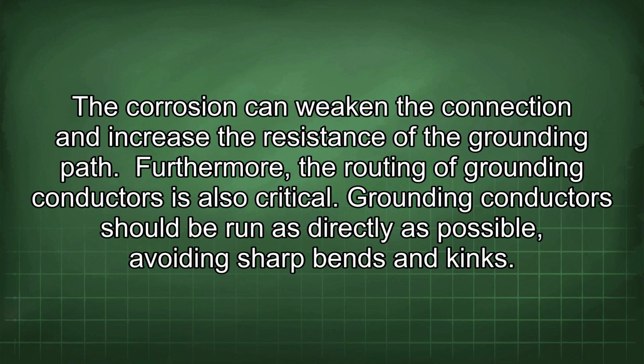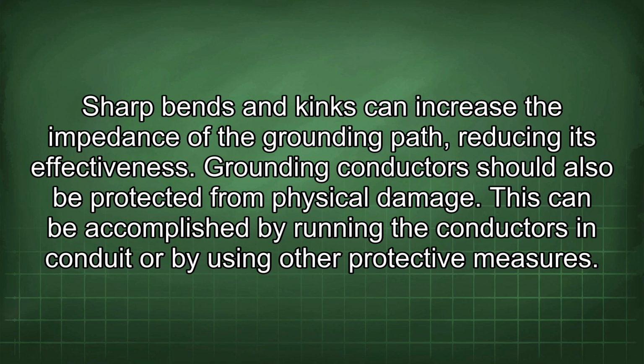Furthermore, the routing of grounding conductors is also critical. Grounding conductors should be run as directly as possible, avoiding sharp bends and kinks. Sharp bends and kinks can increase the impedance of the grounding path, reducing its effectiveness. Grounding conductors should also be protected from physical damage. This can be accomplished by running the conductors in conduit or by using other protective measures.